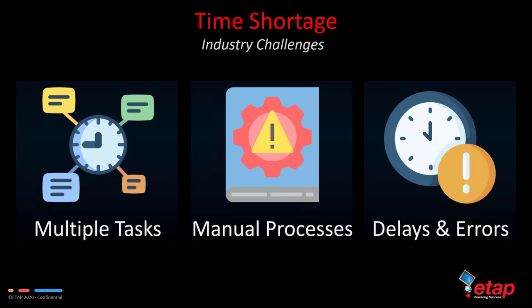Another industry challenge is time shortage. Time shortages are caused by the fact that the entire implementation needs to be done in parallel with your daily work. Some of the processes are manual, such as the process of retrieving settings file, which could include eyeballing of relay settings, especially for electromechanical devices, which make the process slow, time-consuming, and error-prone. In a typical industrial plant, give or take, it may require up to 2 months for complete relay data collection, which essentially adds to the delay in the coordination study, and of course exposes the study to errors that may include transcribing errors or completely missing or skipping some of the protection settings or the protective functions that may need to be collected from the field.